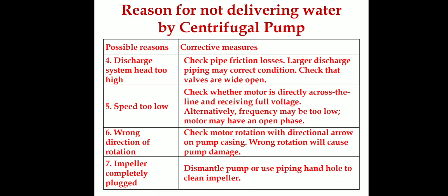The seventh cause is the impeller being completely plugged. If cleaning of the pump is not done properly, the impeller will not work properly and will get stuck. We must ensure regular cleaning to keep the impeller functioning correctly.